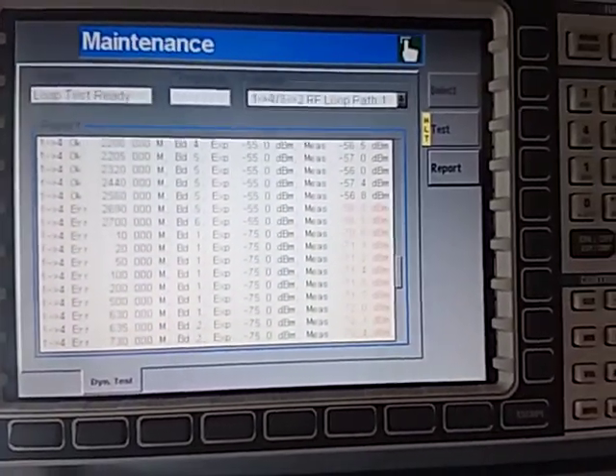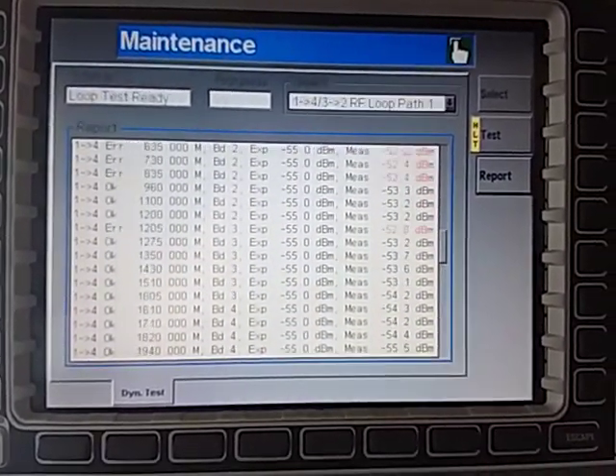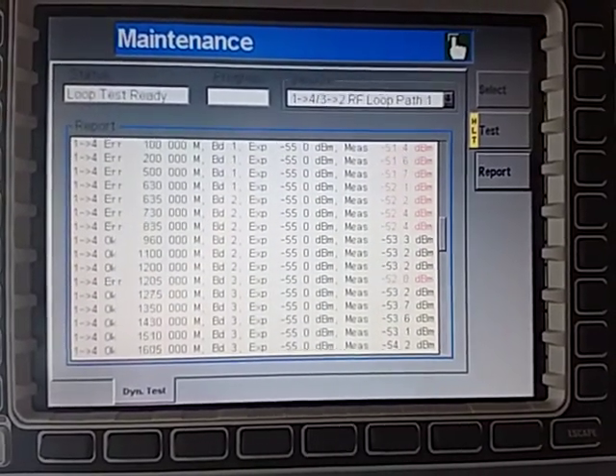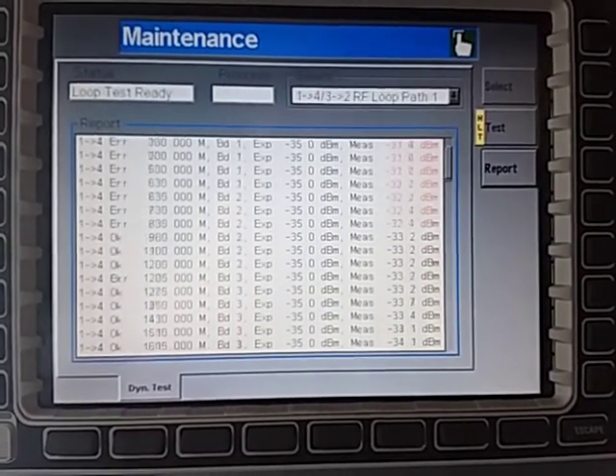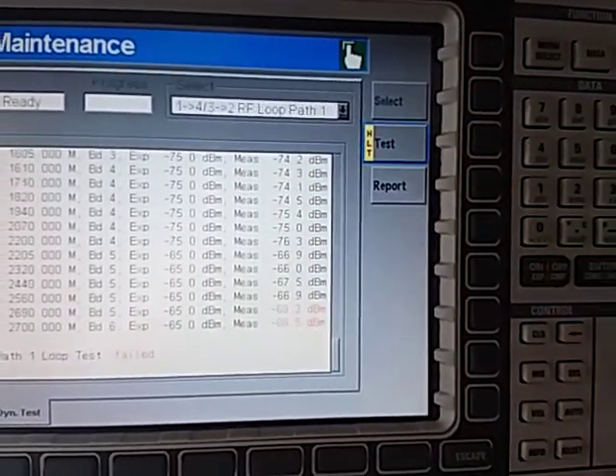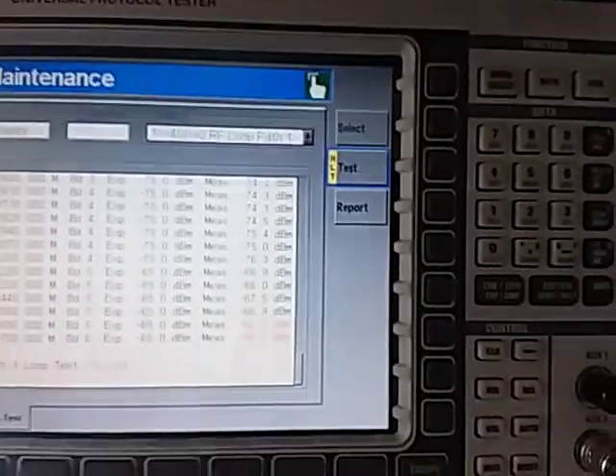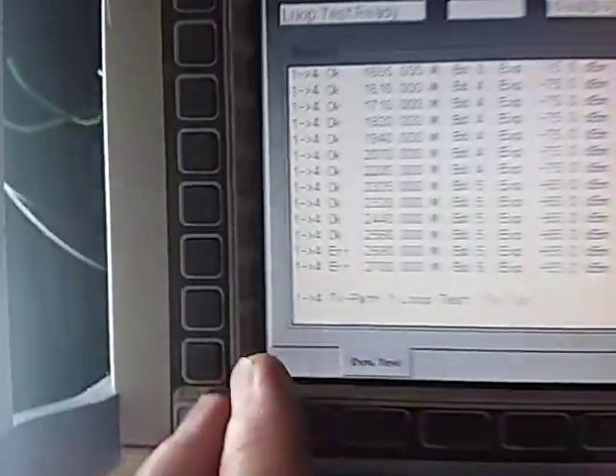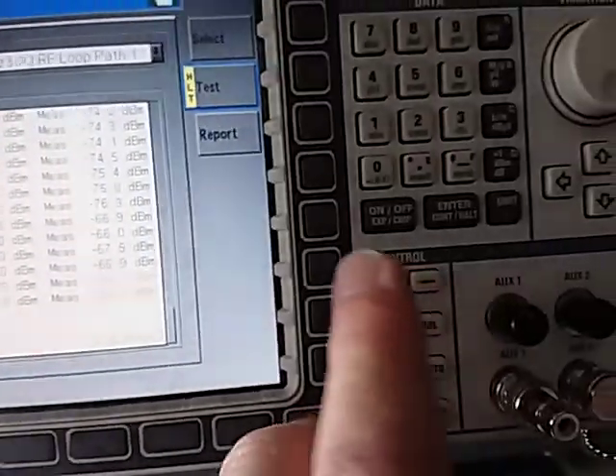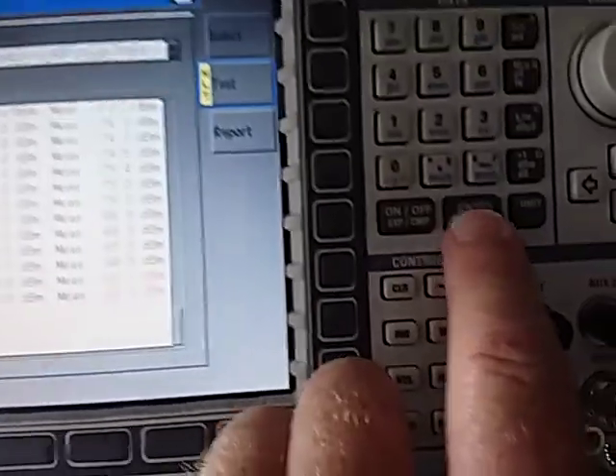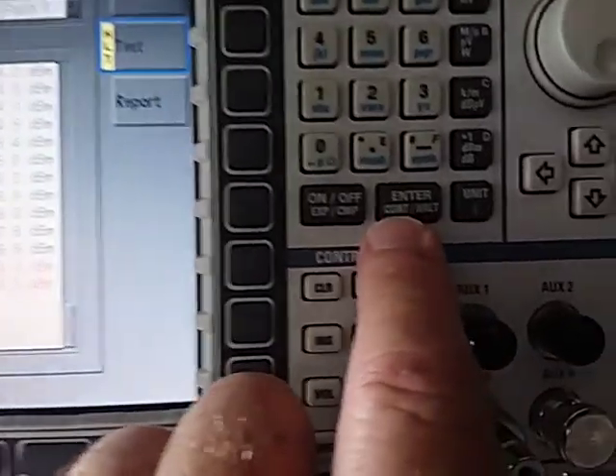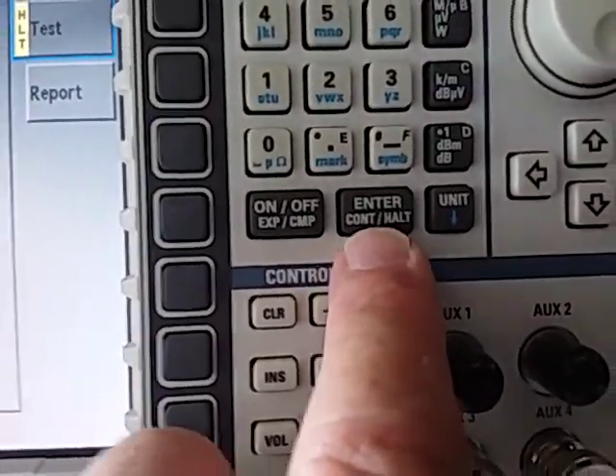What it would pay to do is to have a look and make sure that the variances that you see are within your acceptable parameters. What we've just done is the test on the one to four port. To get the test to do the two to three port, we press the enter button, which you'll note underneath here has got continue or halt. So we're going to continue the test.